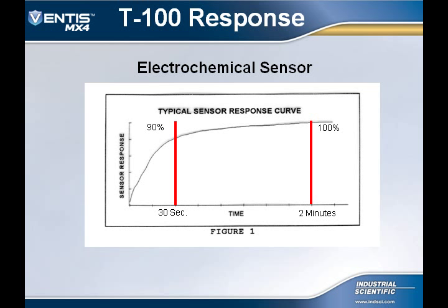What this tells me is that if I'm monitoring an area, I can't just continuously walk around the area to read the presence of gas. What I need to do is stand in one spot and wait at least 2 minutes to make sure that my sensor is seeing 100% of what's in the atmosphere. Once I have waited 2 minutes and my instrument still reads 0, I can now step to the next area that I must monitor and do the same thing over again.